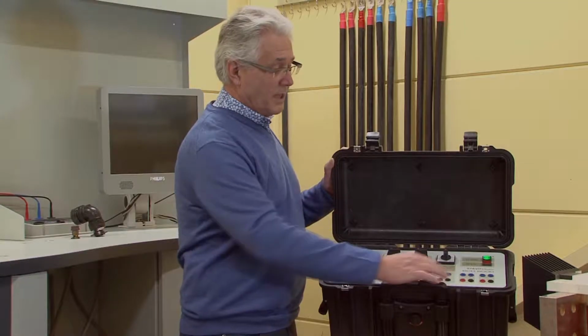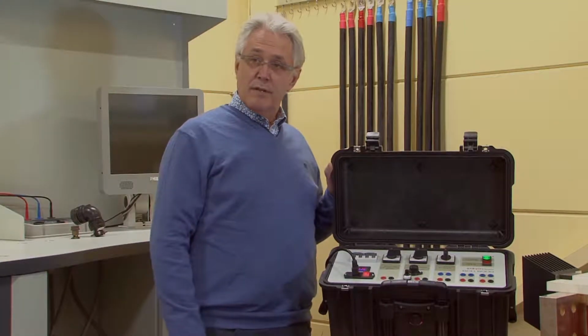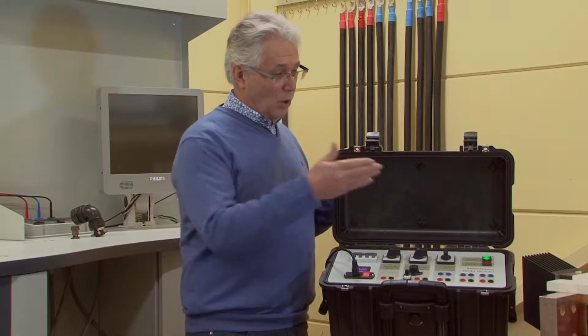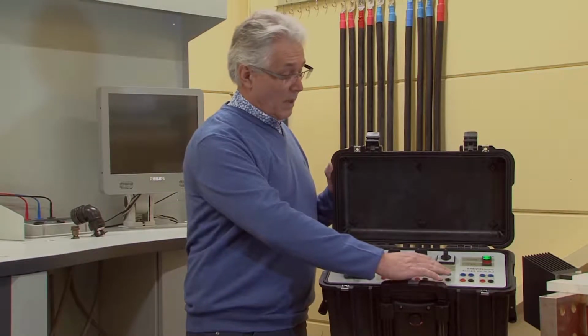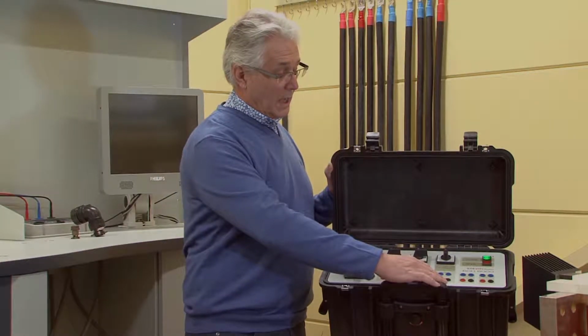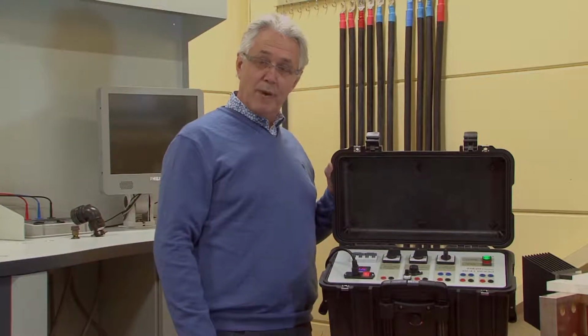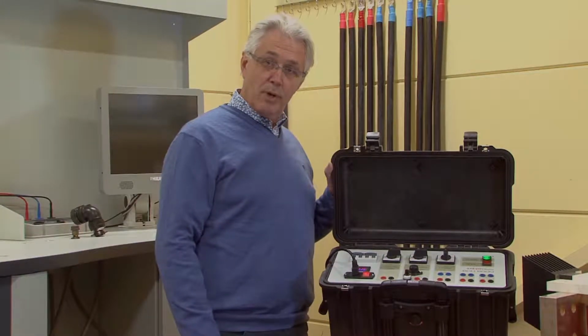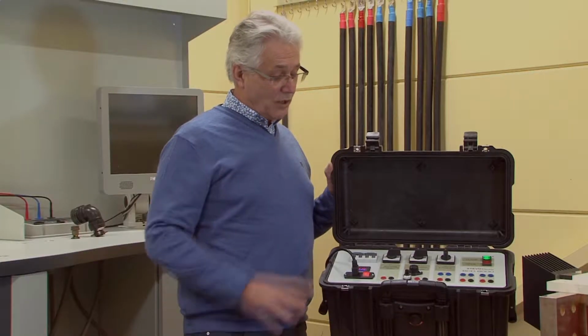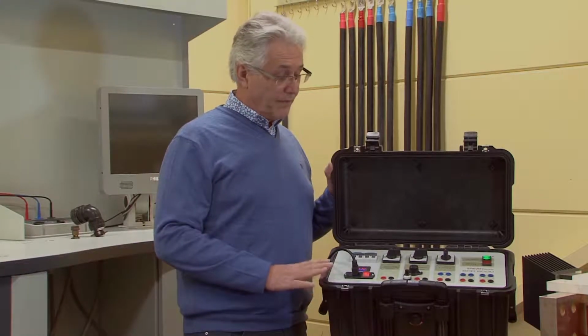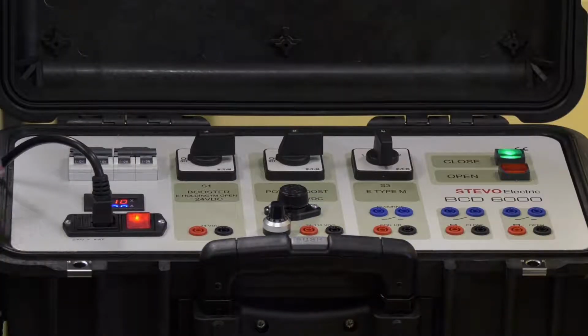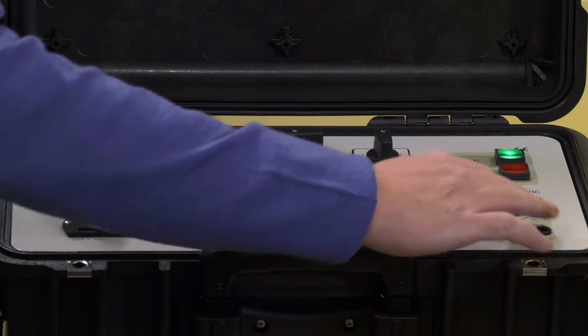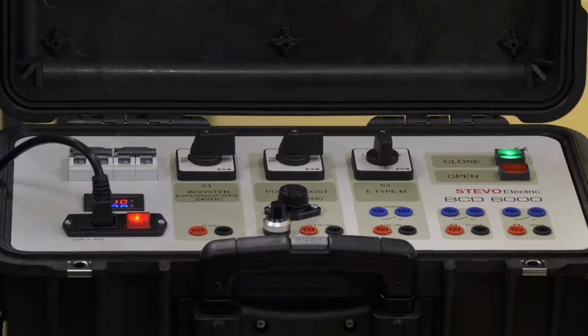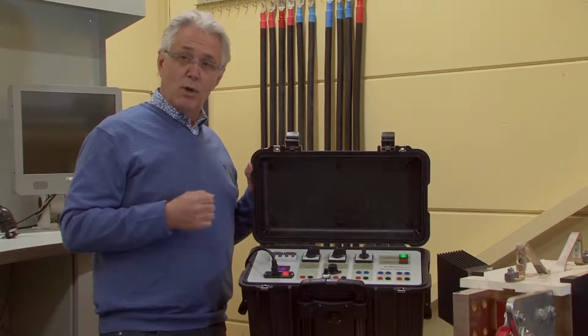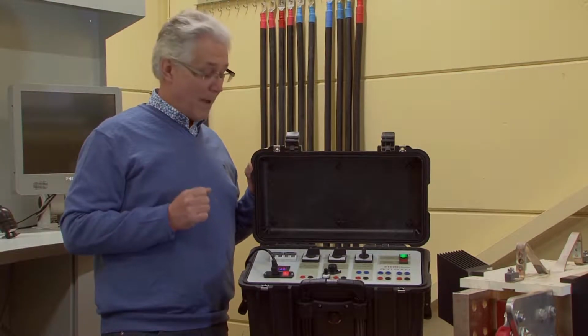Here on this side we see the contacts, the outputs for connecting the coil of the breaker. We support electronic holding type of breakers and magnetic type holding breakers. Actually, the device was developed in order to support any type of circuit breaker. Here are some specific outputs which can be used for a specific type of breakers. All that is explained into our manual.